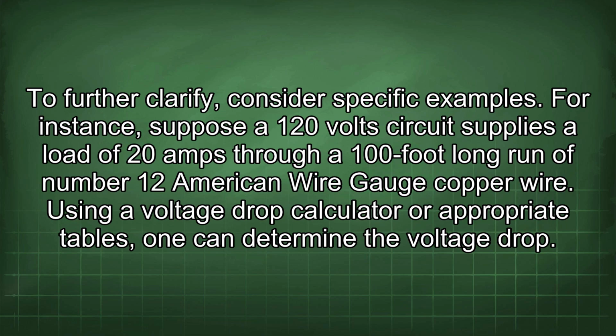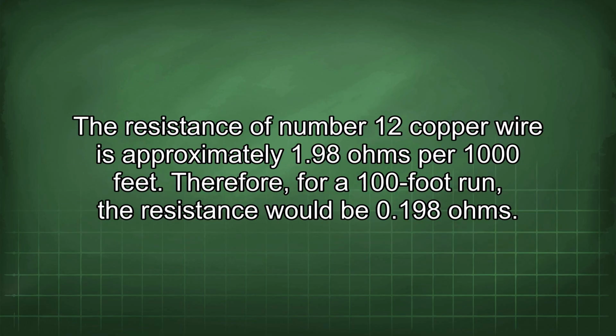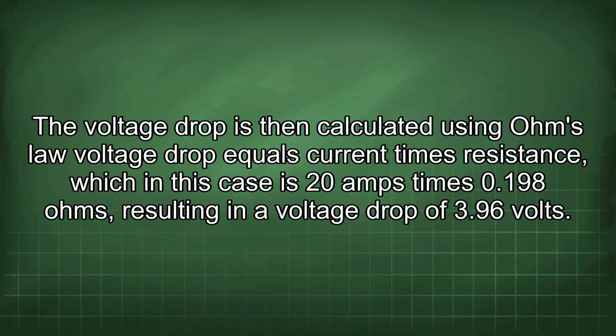Using a voltage drop calculator or appropriate tables, one can determine the voltage drop. The resistance of number 12 copper wire is approximately 1.98 ohms per 1000 feet. Therefore, for a 100-foot run, the resistance would be 0.198 ohms. The voltage drop is then calculated using Ohm's law.